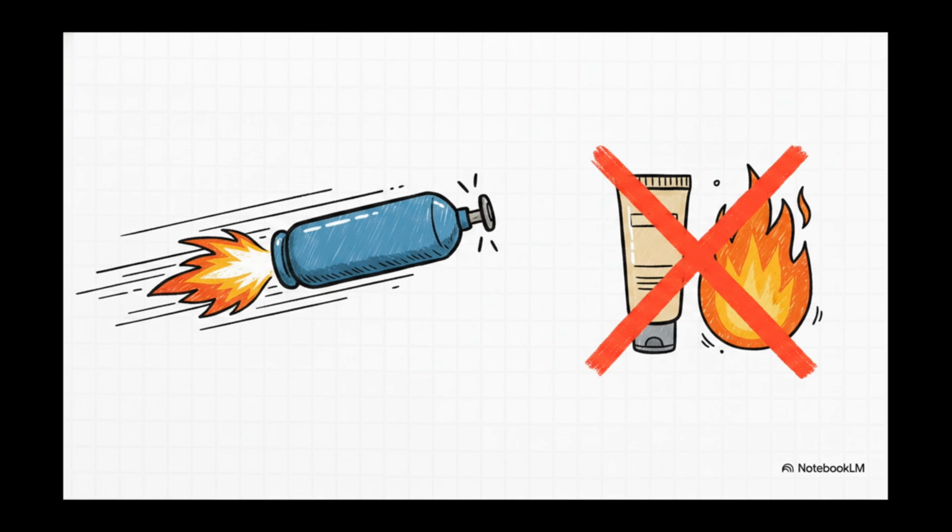And here is an absolutely crucial rule. You cannot, under any circumstances, use tape or petroleum-based products anywhere near this equipment. Mixing pure oxygen with the hydrocarbons in something as simple as lip balm, that creates a massive immediate fire hazard. No smoking, no open flames, and keep those valves closed when you aren't using them.